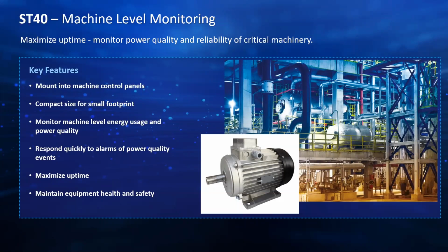We also have the waveform capture capabilities. If there are any noises that are feeding this motor, with the 512 samples per cycle, we can see that, and again, put a filter or some sort of protection on this motor to increase its lifespan.